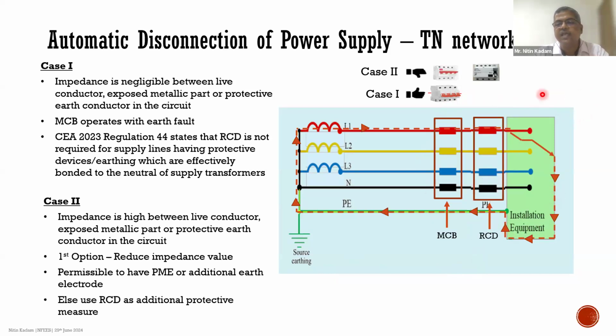There could be a case that the MCB is not tripping because the fault loop impedance value is not sufficiently low. So in that case, the first option is to reduce the impedance value of the circuit.